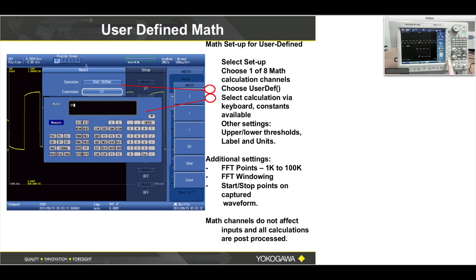Press soft menu button number 7 — next, 1 of 2 — and you'll see other mathematical setups. These are related to averaging, FFTs, and filter setups. You can put constants in here and add or multiply constants. If you have the G2 user-defined math feature, you'll see that in here too.